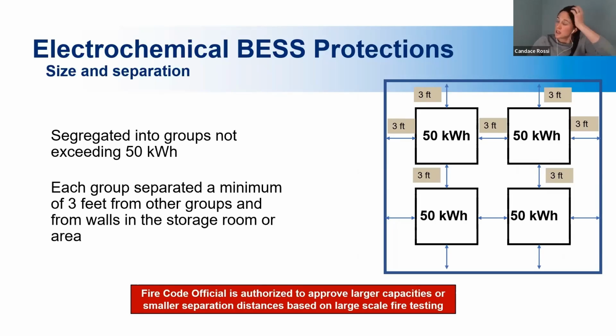All right, so the next that we'll speak about is the size and separation. Basically, all systems will have to be segregated into groups not exceeding 50 kilowatt hours, and each group separated a minimum of 3 feet from the other groups and from walls in the storage room or area. Though the fire code official is authorized to approve larger capacities or smaller separation distances based on large scale fire testing.